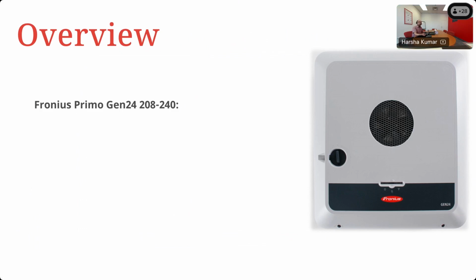Now, one common requirement, which is getting increasingly prevalent in the market, is the requirement for UL 1741 SB. The existing Primos and Simos, which are still being made and sold, do not comply with UL 1741 SB, despite meeting a lot of those requirements, but not entirely. But if you did need to comply with UL 1741 SB, then this model of inverter, the Gen24 Primo single phase alone, does meet that requirement. Okay, so here's a little bit about that.